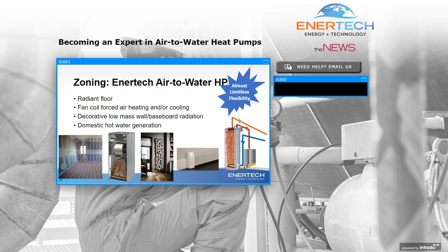But we have the capability of doing radiant floors, Tim mentioned, even some really nice decorative low-mass baseboard and wall-type hydronics. You see in the picture there, second from the left, we can do forced air heating as well as cooling with an air handler that's designed for the temperatures that a heat pump would typically deliver. And on the far right, domestic hot water really is an enormous savings with the type of COPs that we're working with any heat pump, but in particular this air-to-water unit is really designed for heating and for hot water. It does a great job of cooling. But you'll see some of the numbers here on how it performs extremely well in heating and hot water.